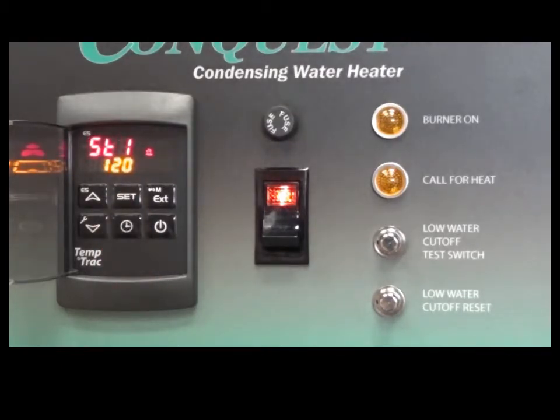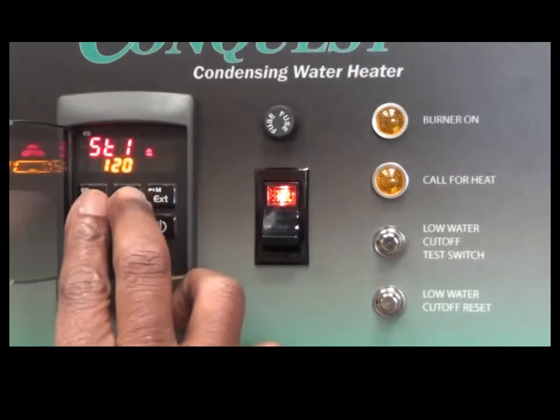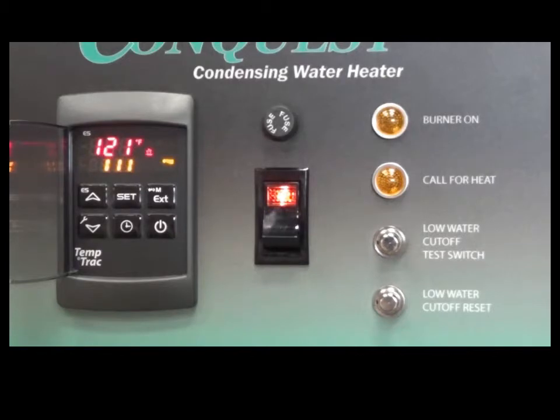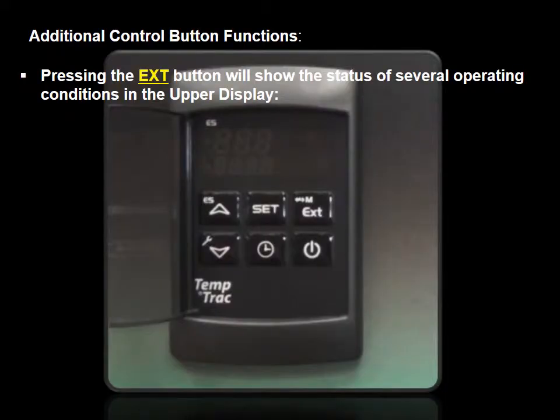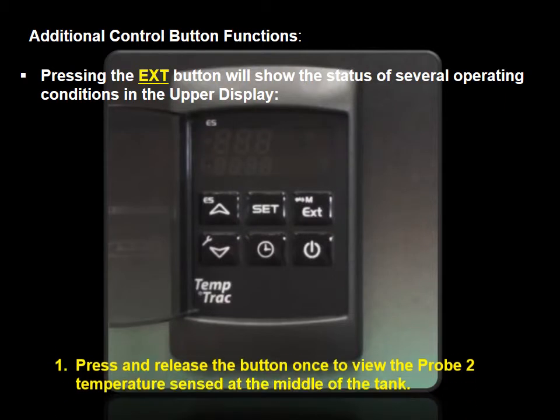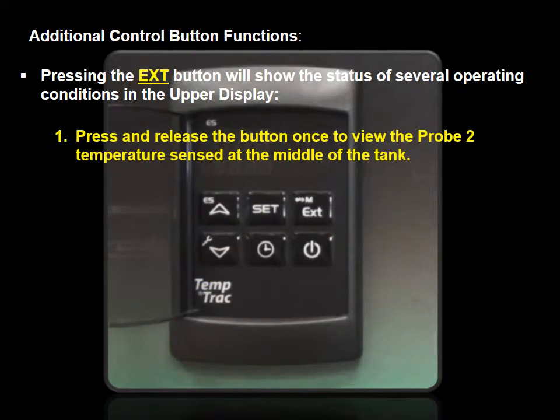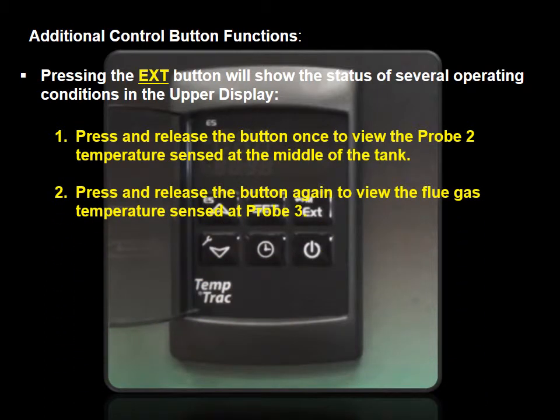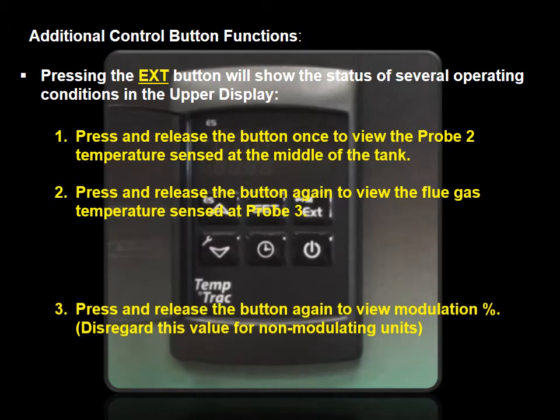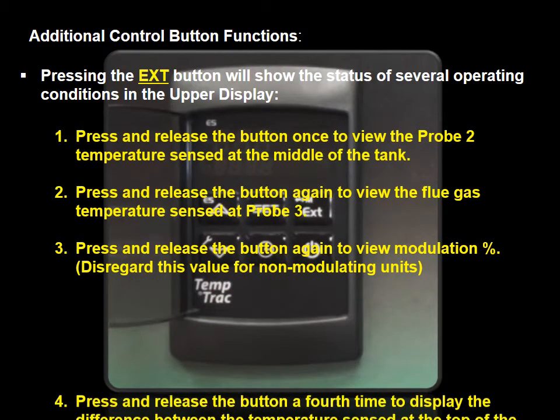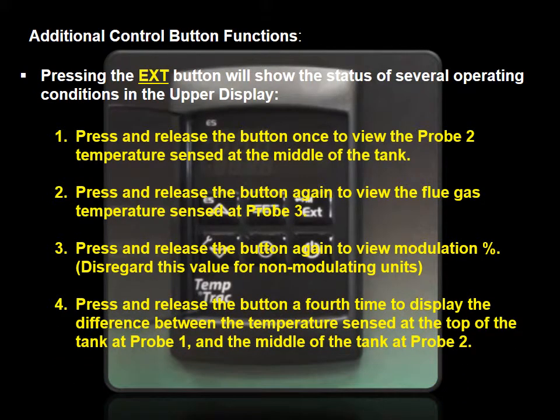By pressing the Set button, we can view the set point value for the stored water temperature we want to maintain. To return to the home screen, press the Set and Up arrow buttons together or wait 15 seconds without pressing any key. Pressing the EXT button will show the status of several operating conditions in the upper display. Press and release the button once to view the Probe 2 temperature sensed at the middle of the tank. Press and release the button again to view the flue gas temperature sensed at Probe 3. Press and release the button again to view the modulation percentage. Disregard this value for non-modulating units. Press and release the button a 4th time to display the difference between the temperatures sensed at the top of the tank at Probe 1 and the middle of the tank at Probe 2.